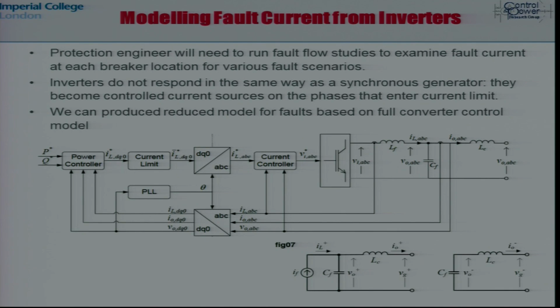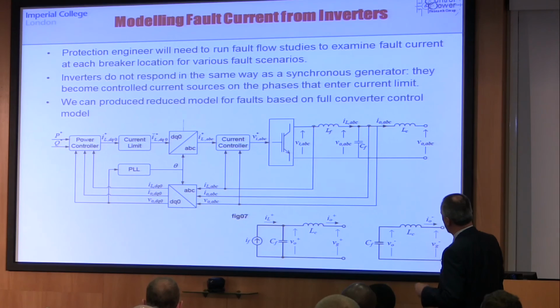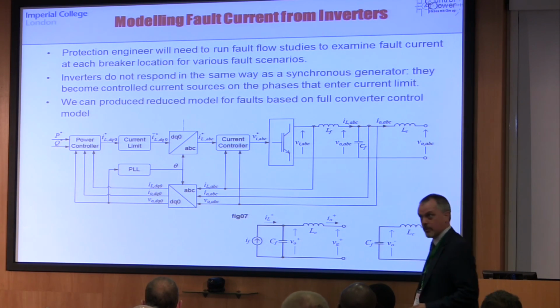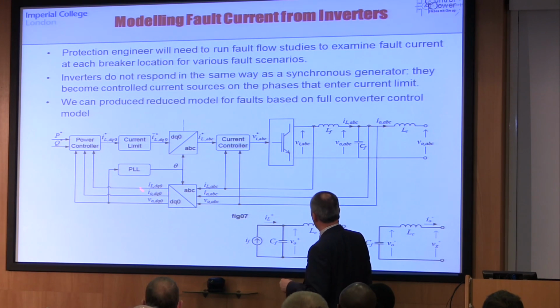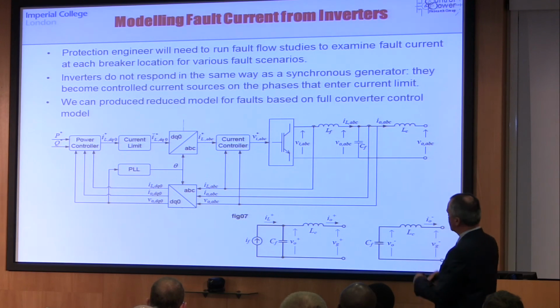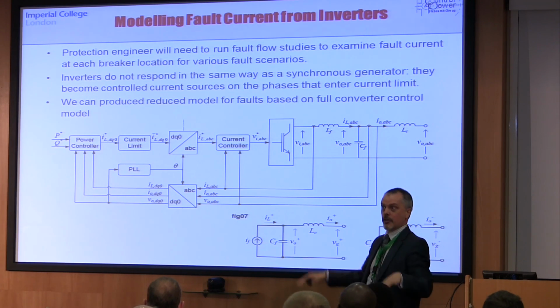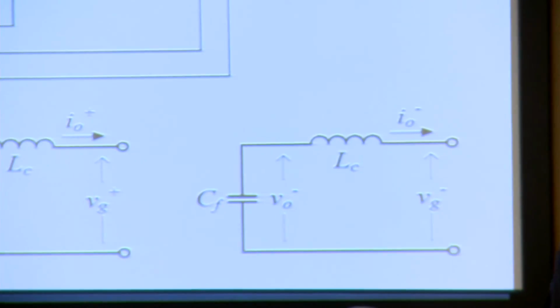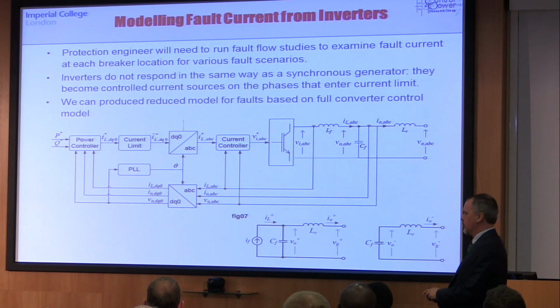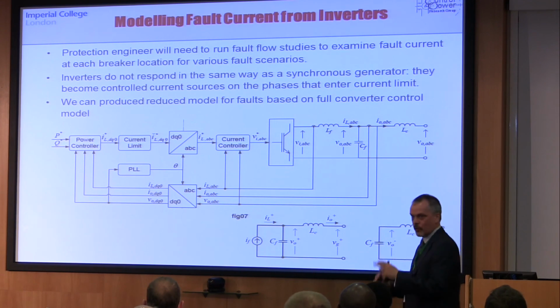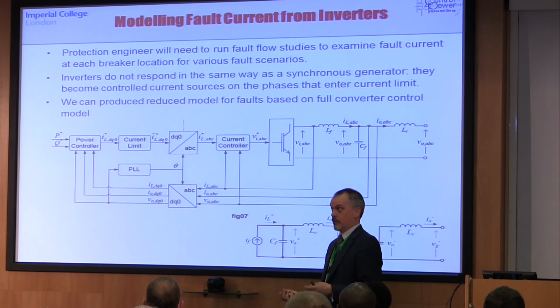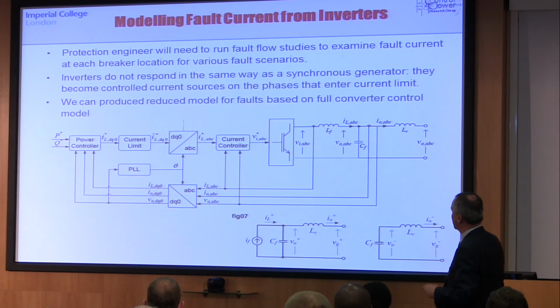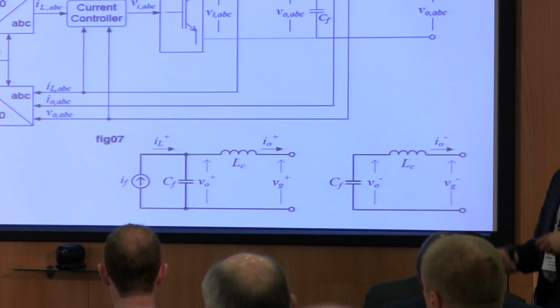So we might look at an inverter in a fault current and think, well, what I need to do then is model my converter, the physical part and the control loops, and then put that in a simulation, throw various faults and look at what happens. So that's quite a complicated system. I mean, we can cope with it, but it's reasonably complicated. But now if you have a feeder of 50 houses and you do that on several substations and you run what would need to be a time domain simulation to find the fault currents, it becomes tedious and is nothing like what a power systems engineer does, which is say that generators behave as voltage sources behind an impedance, and then you calculate the fault currents. So we need to reduce all of that down to something that looks like an equivalent circuit that can go into a fault study.